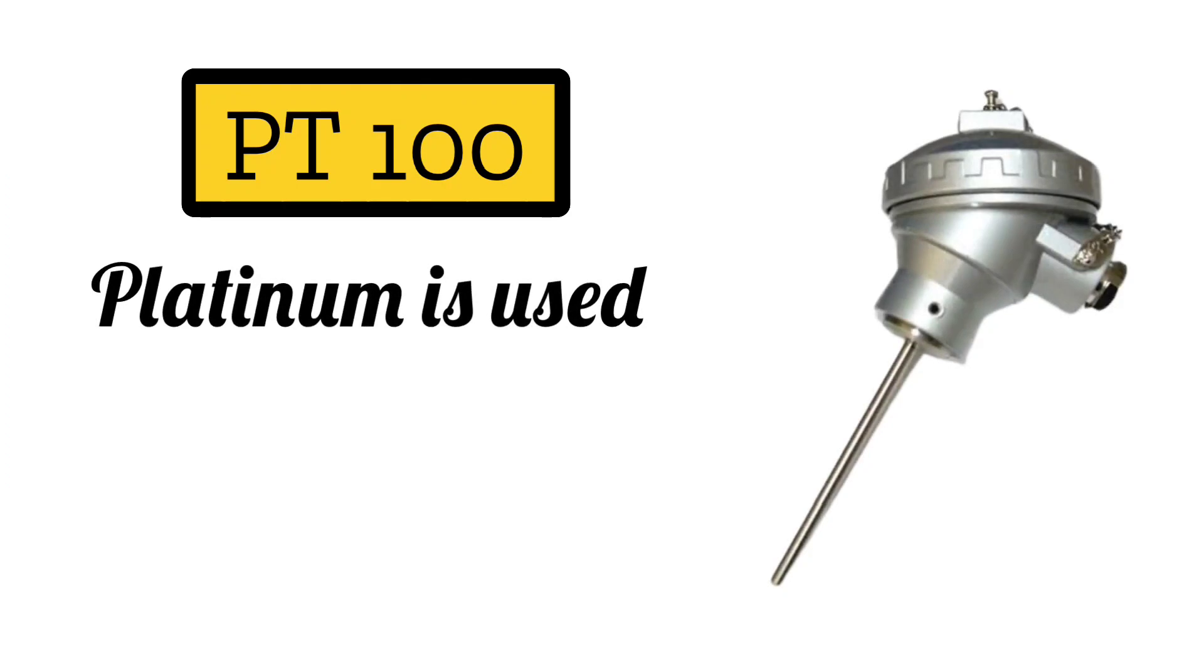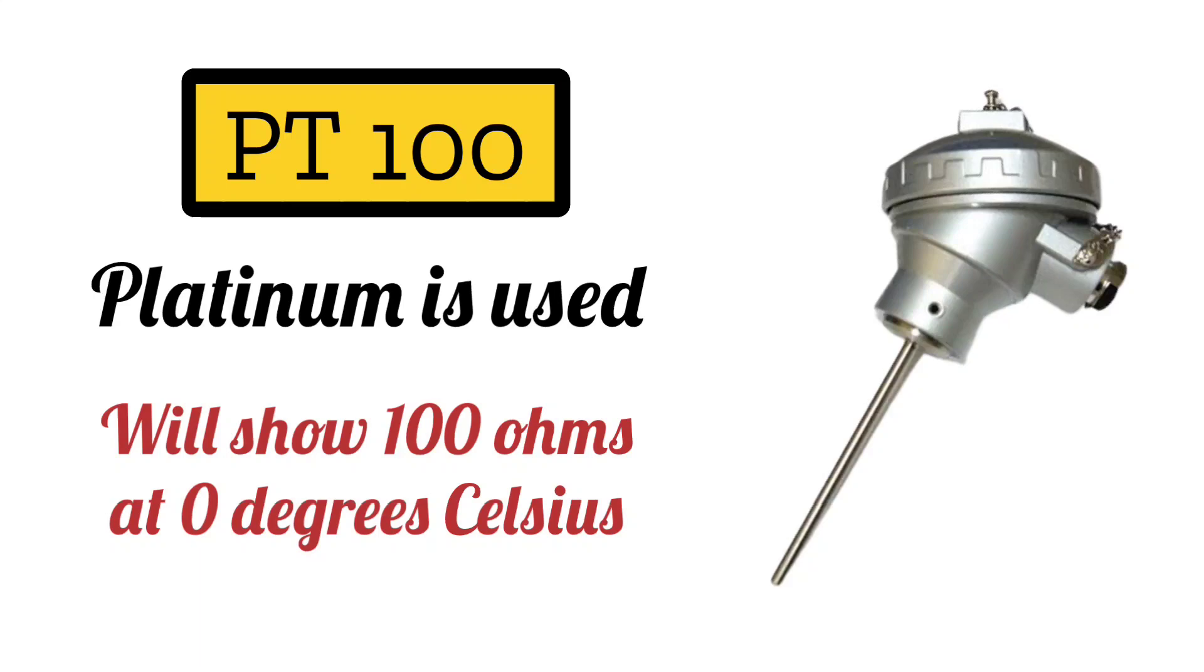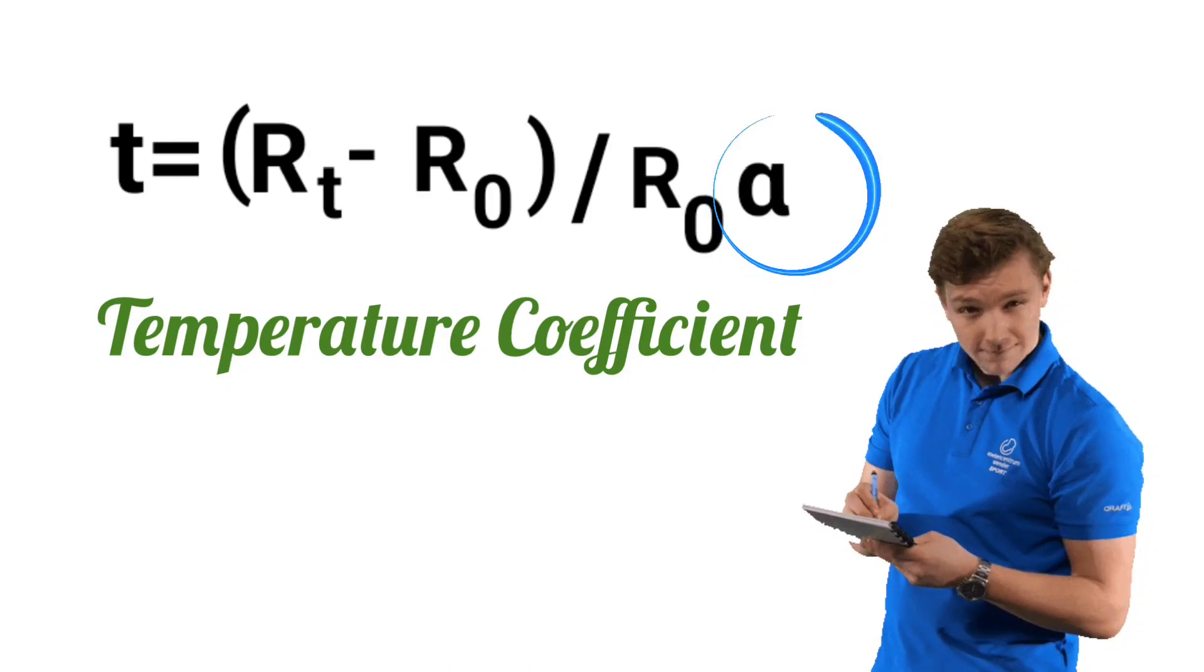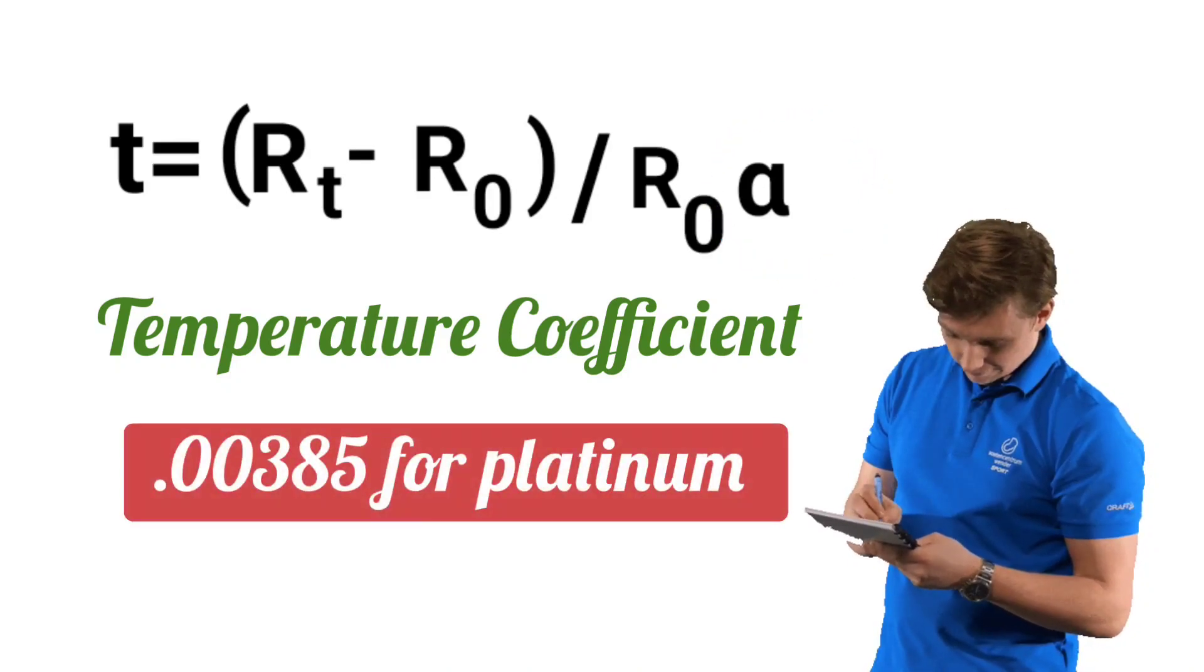PT100 means it's platinum RTD, and it will show 100 ohms at 0 degrees Celsius. Here alpha is the temperature coefficient, whose value is 0.00385 for platinum.